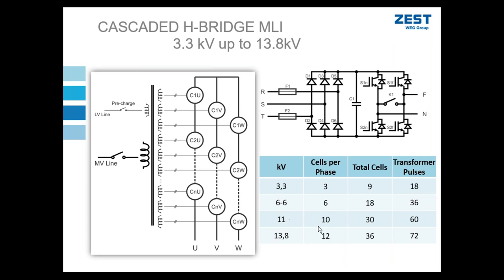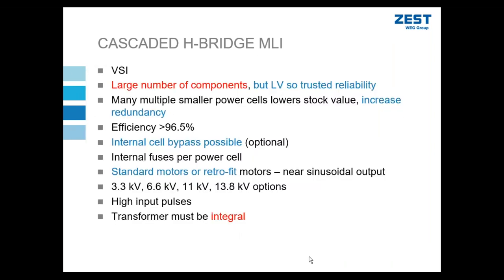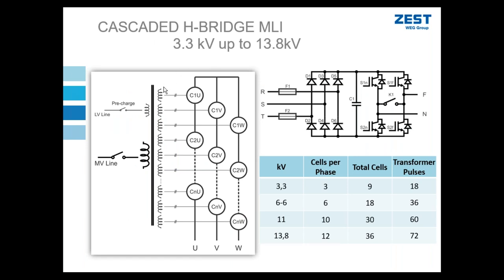All right, and then 11 kV, it's generally done at 10 cells per phase, 30 total cells, and then we can go right up to 13.8 kV. Some characteristics of this topology: it is a voltage source inverter, gives you all the advantages of a voltage source inverter. It has a large number of components compared to a neutral point clamp topology of the same size. Stands to reason, I've got all these additional secondaries, whereas the NPC, I only needed a minimum of 2 secondaries.